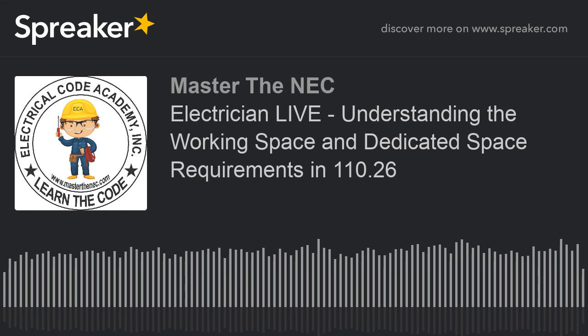Okay? Now, it says, this requirement shall apply to either of the following conditions. Okay, so again, we've established large equipment. It's got to contain overcurrent devices, switching devices, or control devices of some type. And it says there shall be one entrance to and egress from the required working space. And we told you it's got to be 24 inches wide and 6.5 feet high. And it has to be at each end of the working space. Now, the requirement shall apply to either. So we just gave you the rules. Now we're going to tell you how they apply.